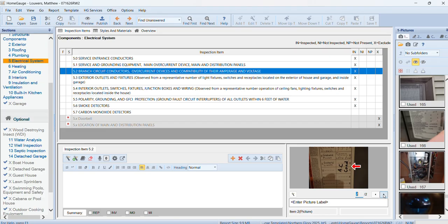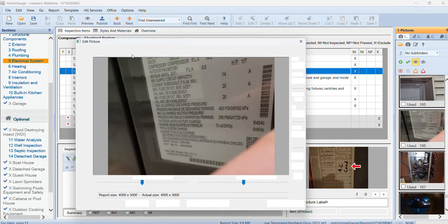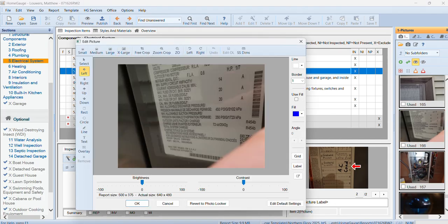Okay, so I think we're good because this is the maximum. Oh, well, right here: minimum circuit ampacity, that's this. Maximum overcurrent, so this is maximum overcurrent.